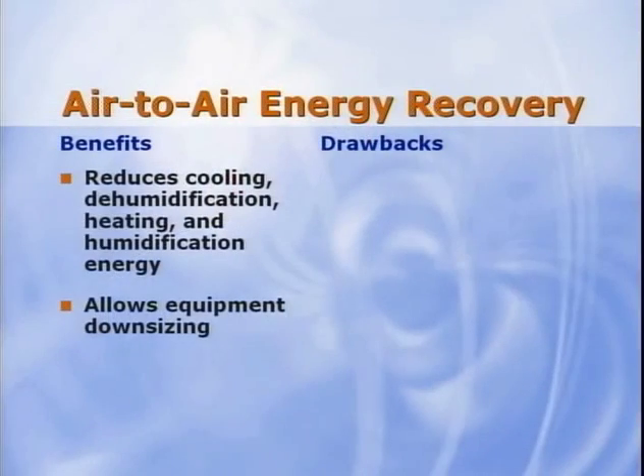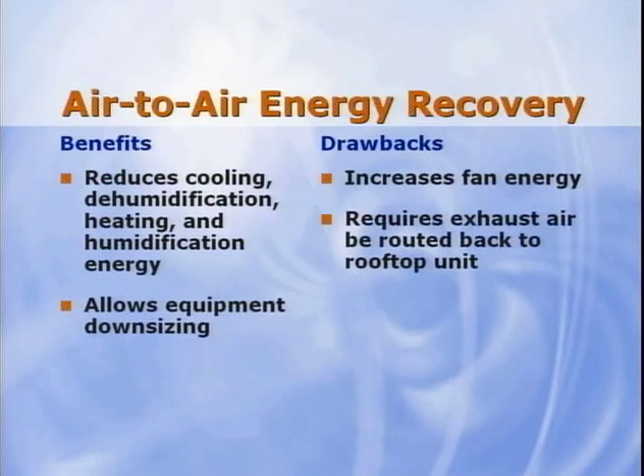First, the wheel adds pressure drop, which can increase fan energy. The operating cost savings provided by recovering energy must exceed the increased cost of operating the fans in order to justify the cost of the energy recovery device. Also, routing the exhaust air back to the rooftop unit may require more ductwork and ceiling space than a system without energy recovery. When using energy recovery to precondition outdoor air, consider these following general recommendations.